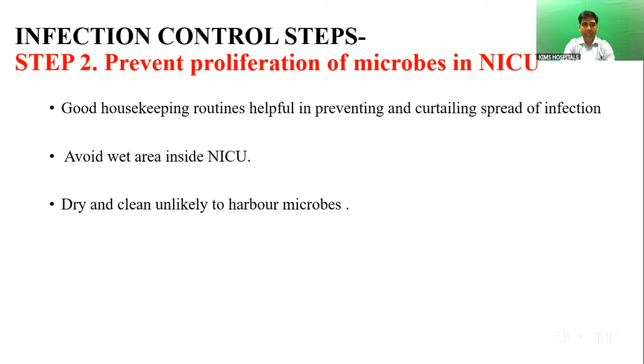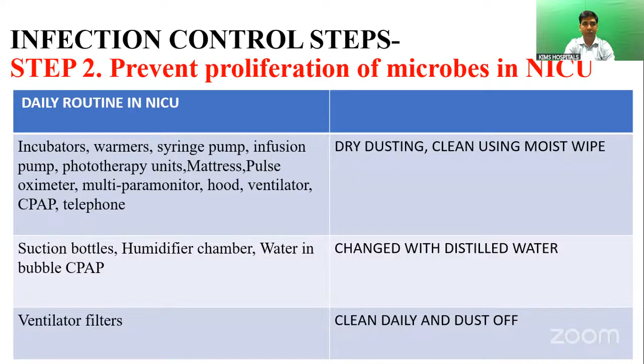In the daily routine, all the equipment, such as the incubator, warmer, syringe pump, infusion pump, phototherapy unit, mattresses, pulse oximetry, multiparameter monitor, hoods, ventilator, CPAP and telephone, should be cleaned with a moist wipe after dry dusting if the baby is not inside that crib, incubator or warmer. The suction bottle, humidifier chamber and water in the bubble CPAP should be changed with distilled water. The ventilator filter should be cleaned and dusted off daily. Bag and mask should be immersed in 2% Cidex for 6 to 8 hours, after dismantling and cleaning with running water. Incubator and warmer should be cleaned with Bacillocid if not occupied by infants.